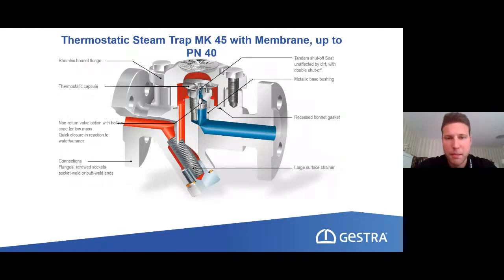So here we have the membrane type steam trap. It's an MK45 with the membrane. It's the same membrane, as I said, as on the control unit of a ball float steam trap. So it's another thermostatic one, which is also capable of doing the air venting very well. If you take a look at the body of the steam trap, it looks very much like the BK, like the bimetallic steam trap. Only the top of the body is a little different. It's flat compared to the BK, which has a different shape, but the body itself looks similar. And the condensate travels through a strainer to the membrane, to the capsule, and it now detects the current temperature, and by the temperature it will discharge the condensate.